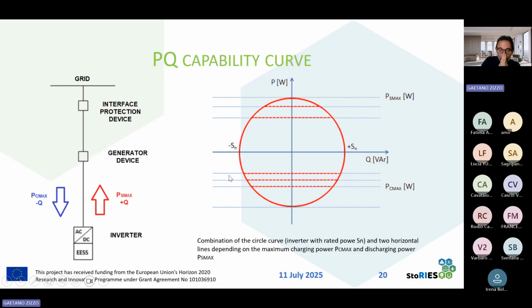And focusing on batteries, this is the case of a battery with its inverter that can inject a given active or reactive power into the grid, or can absorb from the grid an active or reactive power. And varying these quantities, the storage system can regulate the voltage at this node.